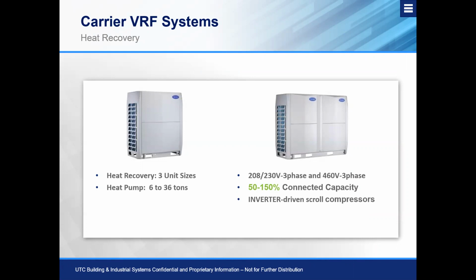But the nice part with this, if you look at the slides up there, is that they come in a single base rail application, which means we're not twinning or having triple modules together, which require twinning kits. With the twinning kits, there is more room for error, and there also are more brazing joints on the system, which could be more potential leak areas. So the nice part is we eliminate the twinning kits. We eliminate the time that it takes to actually join units, whether it be a twin or a triple configuration.